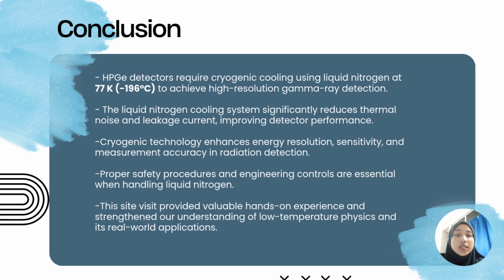So, in conclusion, this site visit provided us with insight into the application of cryogenic technology in scientific research and radiation detection. We learned that HPGE detectors require liquid nitrogen cooling at 77 Kelvin to minimize thermal noise and leakage current, allowing the detector to achieve excellent energy resolution and accurate gamma measurement. Through this visit, we also gained a better understanding of important physics concepts such as heat transfer, thermal excitation suppression, latent heat of evaporation, and electronic noise reduction. In addition, we observed the importance of safety practices and engineering controls when handling cryogenic liquids such as liquid nitrogen. Overall, this experience successfully connected the theoretical concepts learned in class with practical industry and research applications, enhancing our knowledge of low temperature physics and superconductivity.